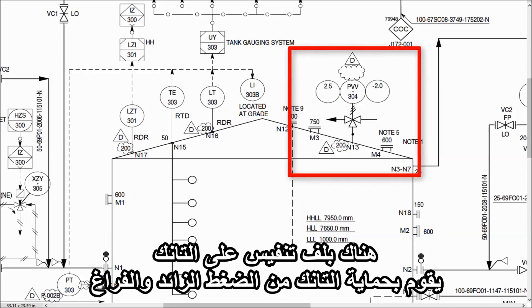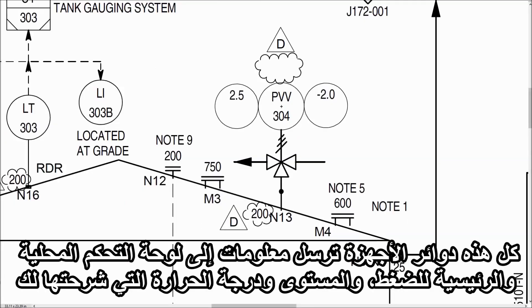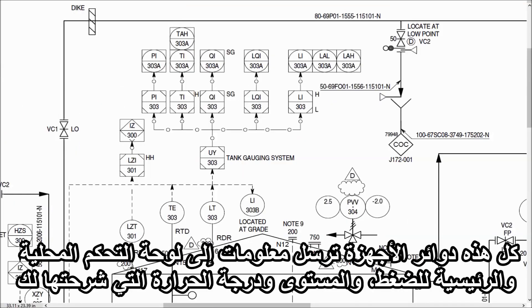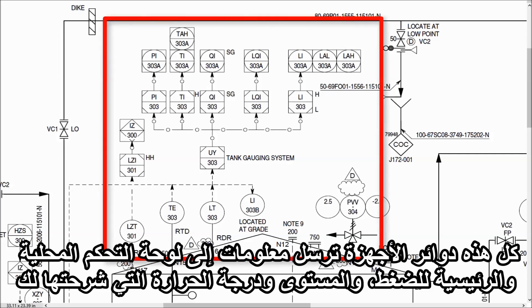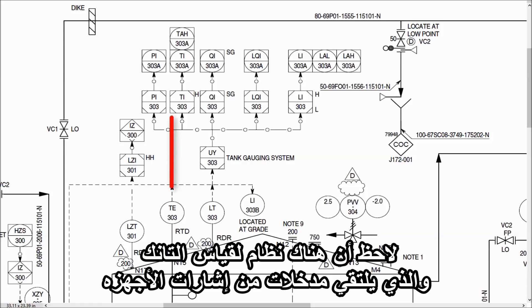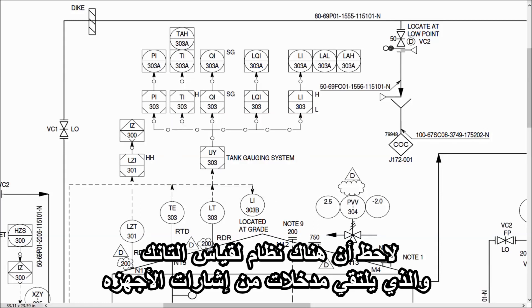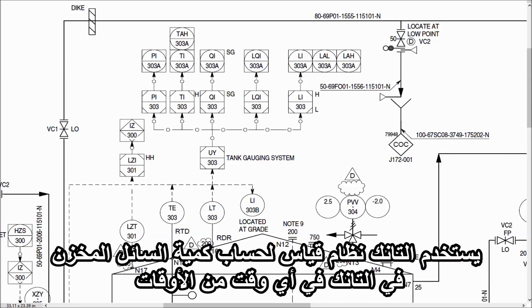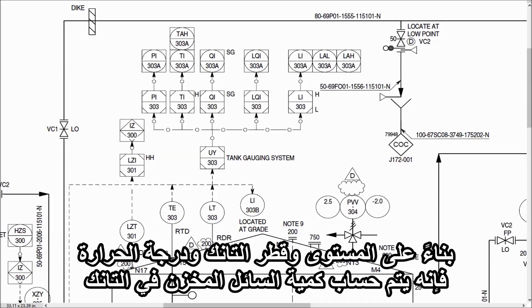There is a breather valve on the tank, which protects the tank from overpressure and vacuum. All these instrument bubbles send information to the local and main control panel for the pressure, level, and temperature instruments explained earlier. You may have noticed there is a tank gauging system that receives all input signals from the instruments. The tank gauging system is used to calculate the quantity of liquid stored in the tank at any given time — based on diameter, level, and temperature, it calculates the quantity stored.